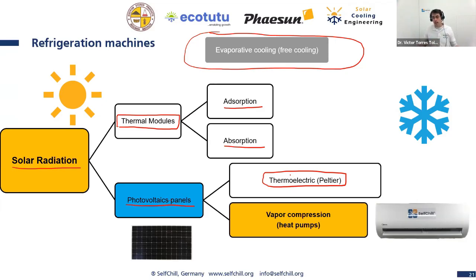And the focus of today, are vapor compression heat pumps. This is actually the most used cooling system, conventional refrigeration systems. As you know, they always have a compressor, and they are compressing a refrigerant and producing the cooling effect. They are called, by the way, heat pumps. If you don't know why they are called heat pumps, no worries, you are going to understand why today.